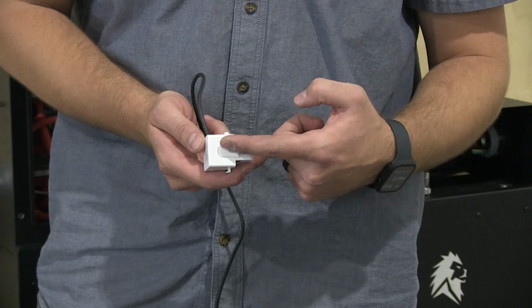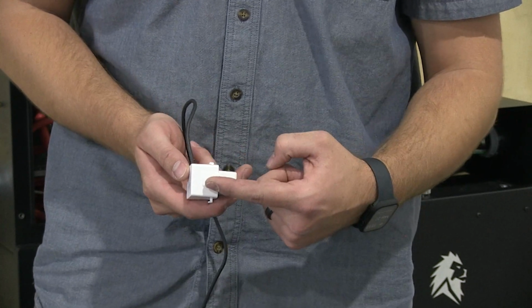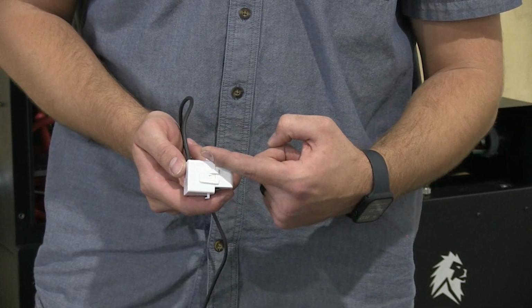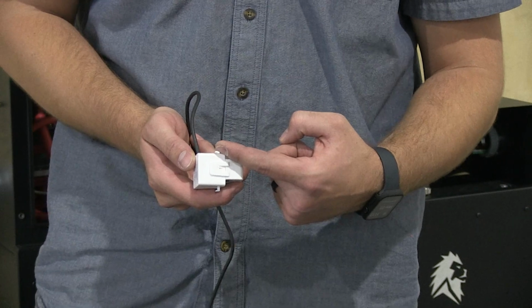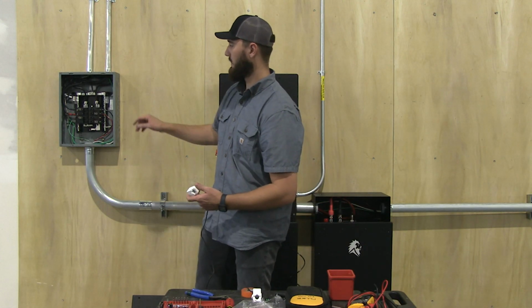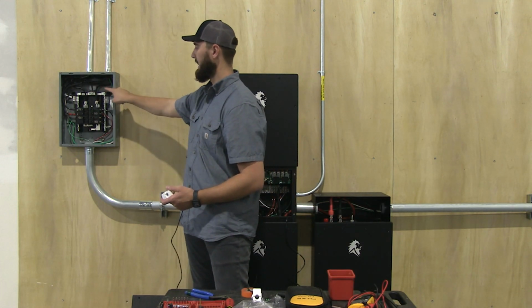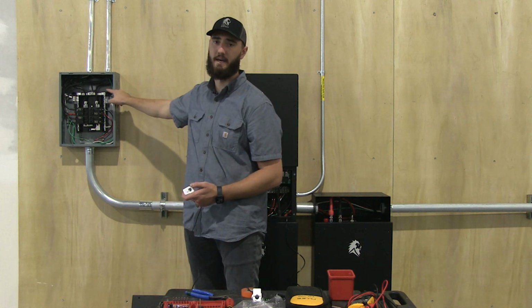For installing our CTs, we're going to have the arrow face away from the inverter, or towards the utility, and they're going to be located on L1 and L2 of our main panel.